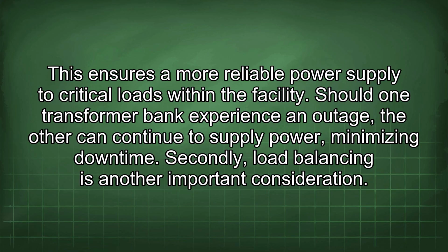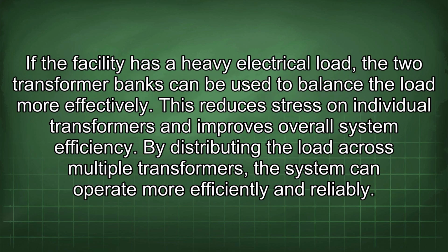Secondly, load balancing is another important consideration. If the facility has a heavy electrical load, the two transformer banks can be used to balance the load more effectively. This reduces stress on individual transformers and improves overall system efficiency. By distributing the load across multiple transformers, the system can operate more efficiently and reliably.